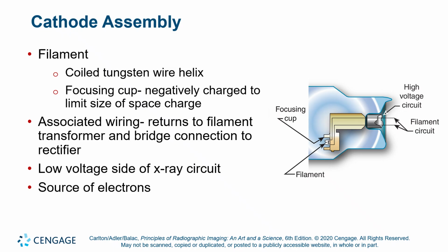So there's usually 3 wires running into the filament. 2 of the wires go to the ends of the step-down transformer in the filament circuit. The middle wire is connected to the bridge. It's the bridge connection that is a fork in the circuit, so to speak, to connect back to the rectifier and the high voltage transformer. Okay. So the bridge connection is dead until the exposure switch is pressed, and then the bridge connection takes over the filament circuit. Okay.